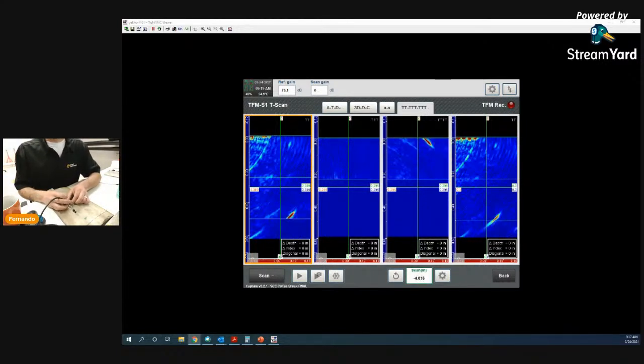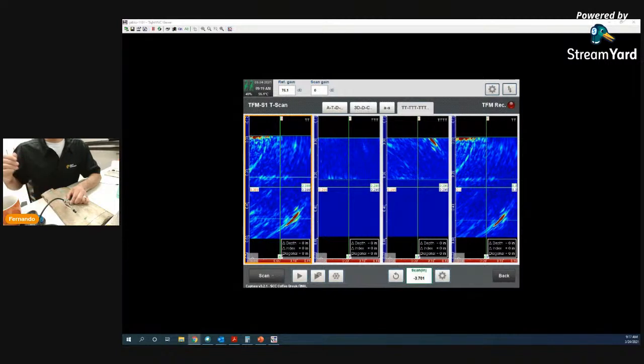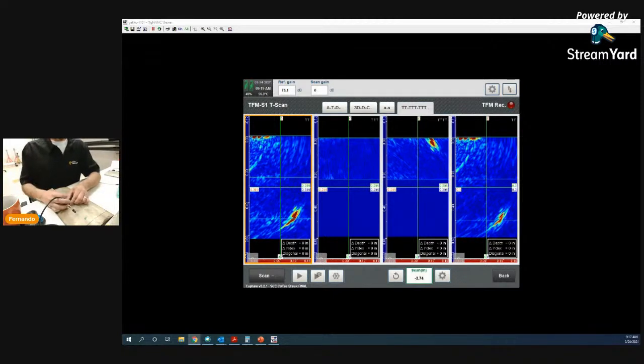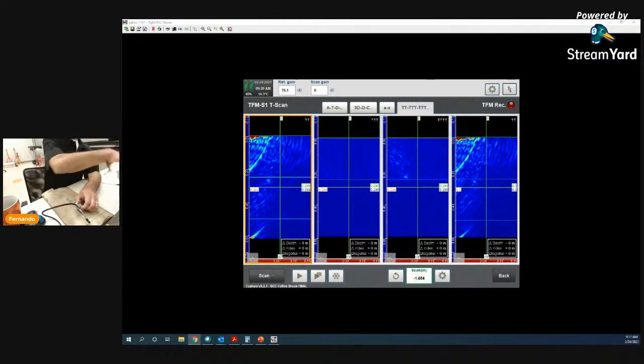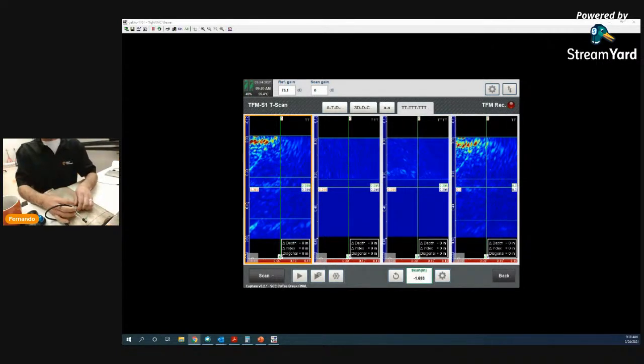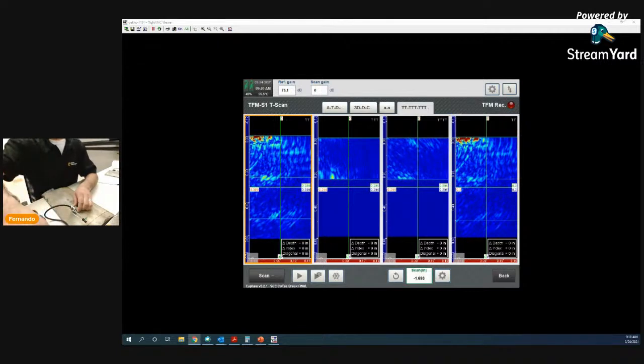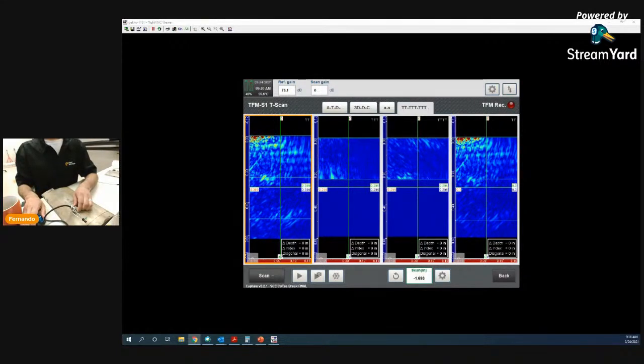So let's go through this thing. As you can see on the image here, you can see as I'm adjusting it on my piece, there's a tip on one of these cracks that we see here. So I'm actually going to put more coupling on this. Let's do a scan. I'm going to reset the encoder here, so it starts at 0. I'm going to hit play and scan.